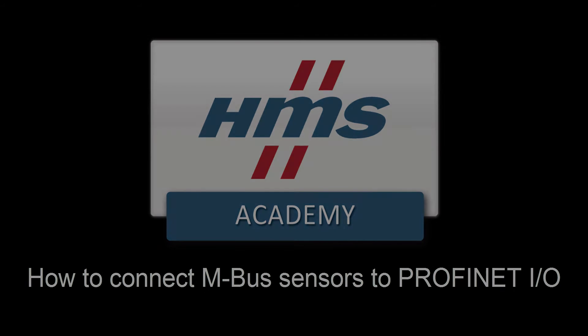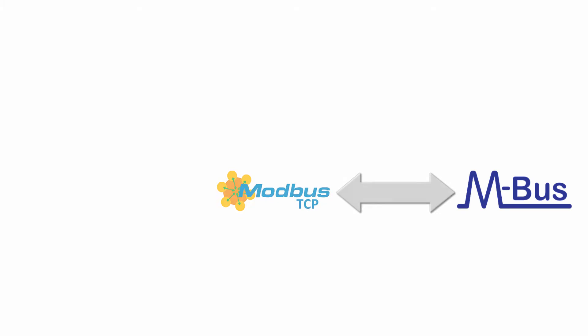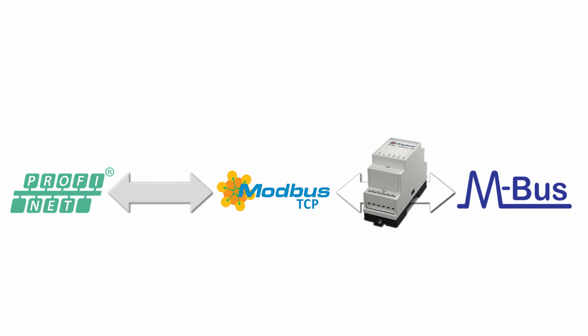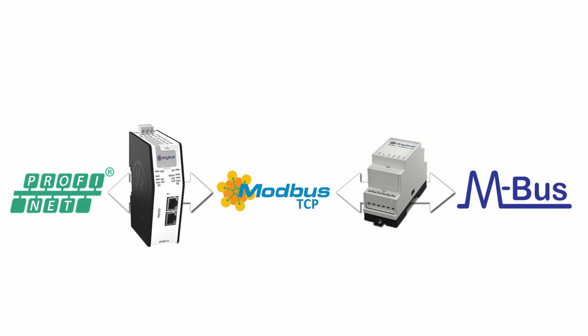To be able to do this, we will first convert the MBUS values to Modbus TCP registers with the help of Anybus MBUS to Modbus TCP gateway, and then convert the Modbus TCP registers to PROFINET I.O. using the Anybus X gateway Modbus TCP.